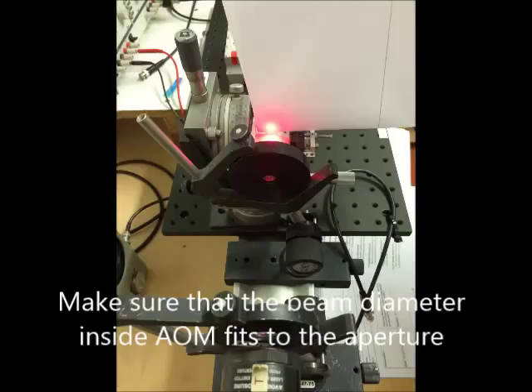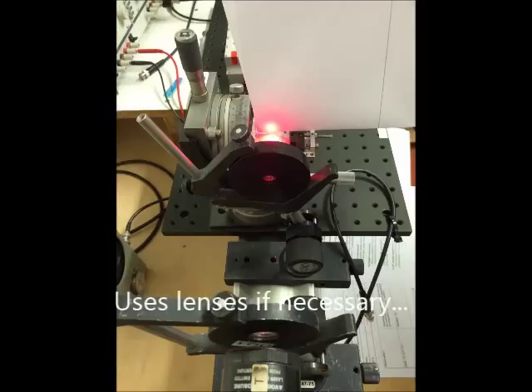Make sure that the laser beam diameter inside the modulator fits to the aperture of the modulator. If necessary, you can use lenses to collimate or focus the laser beam to the desired diameter.